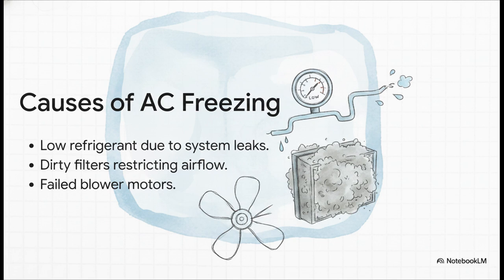Basically, this freezing happens when your system just can't breathe or cool properly. It's usually due to low refrigerant from a system leak, dirty filters that severely restrict airflow, or a dead blower motor. And that high Indiana humidity makes the ice formation so much worse. The crucial point here is, if you see ice, you need to shut the system down immediately to save your compressor from destroying itself.